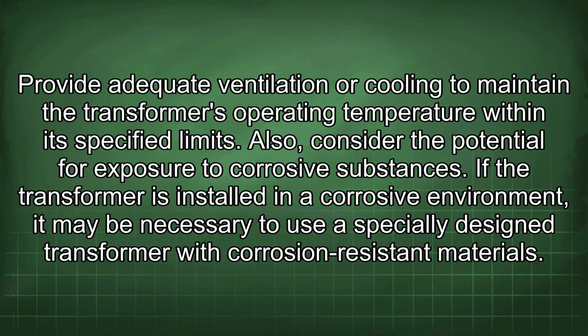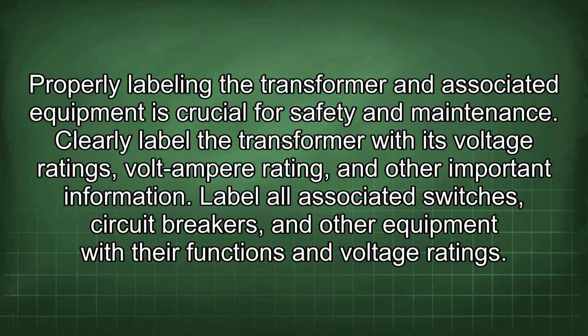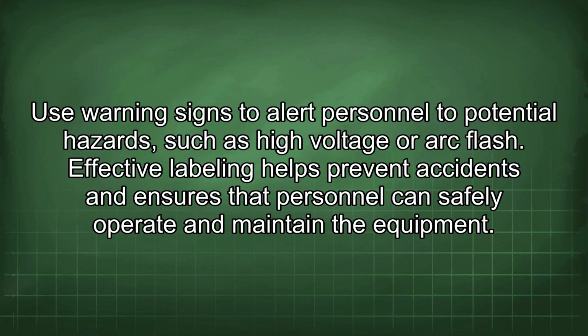Also, consider the potential for exposure to corrosive substances. If the transformer is installed in a corrosive environment, it may be necessary to use a specially designed transformer with corrosion-resistant materials. Properly labeling the transformer and associated equipment is crucial for safety and maintenance. Clearly label the transformer with its voltage ratings, volt-ampere rating, and other important information. Label all associated switches, circuit breakers, and other equipment with their functions and voltage ratings. Use warning signs to alert personnel to potential hazards, such as high voltage or arc flash. Effective labeling helps prevent accidents and ensures that personnel can safely operate and maintain the equipment.